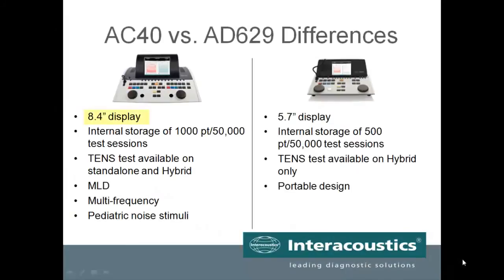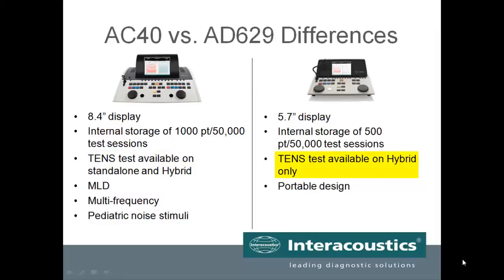Additional differences include a larger display of 8.4 inches on the AC40 versus the 5.7-inch display on the AD629. Both devices have internal storage, but there is 1,000 patient storage for the AC40 versus 500 on the AD629. Differences in the testing function include the TENS test, which is available in both standalone and hybrid models on the AC40, but only the hybrid model for the AD629.